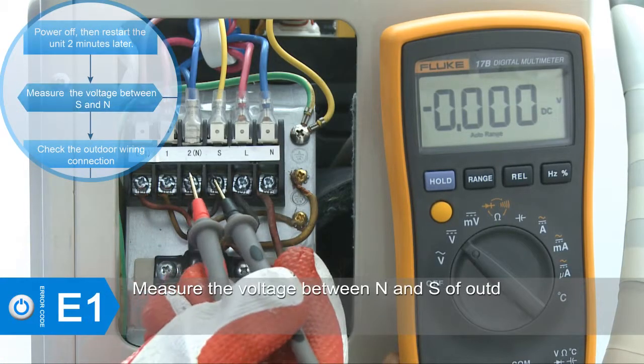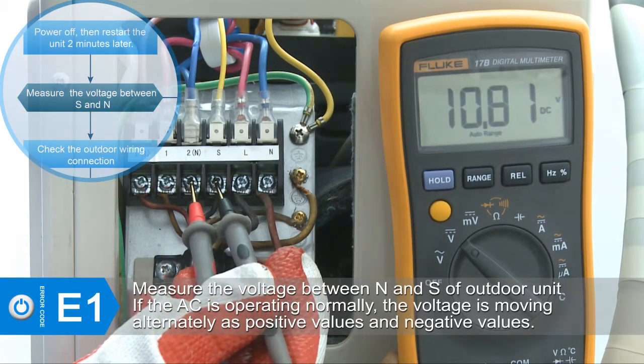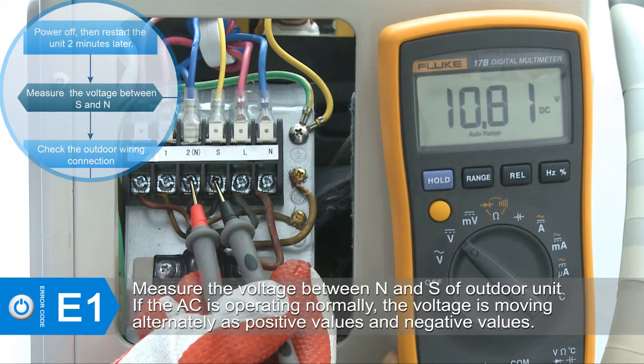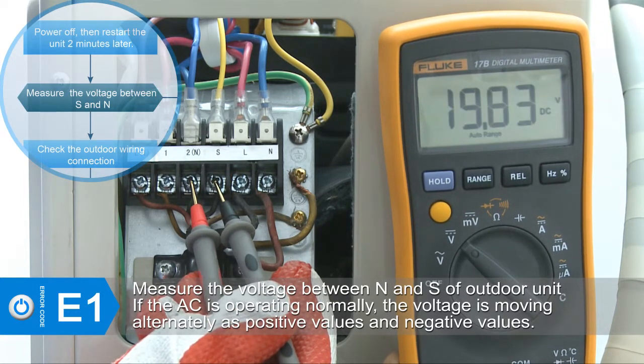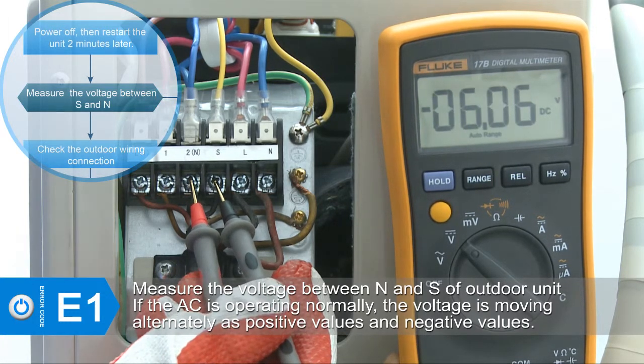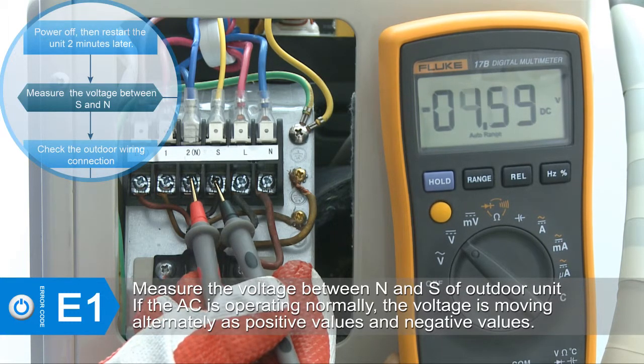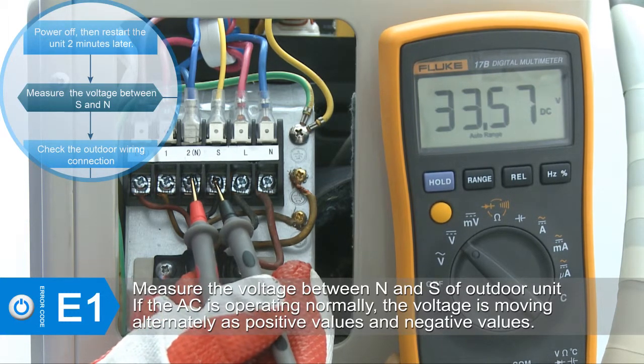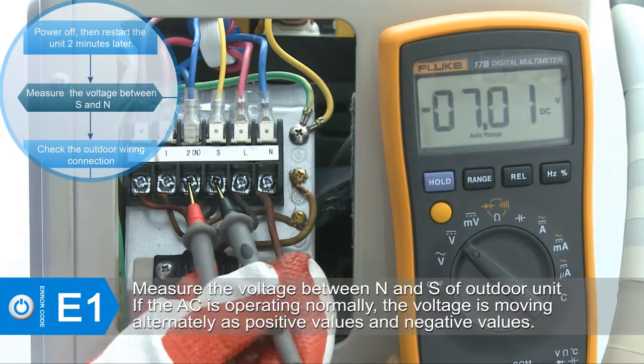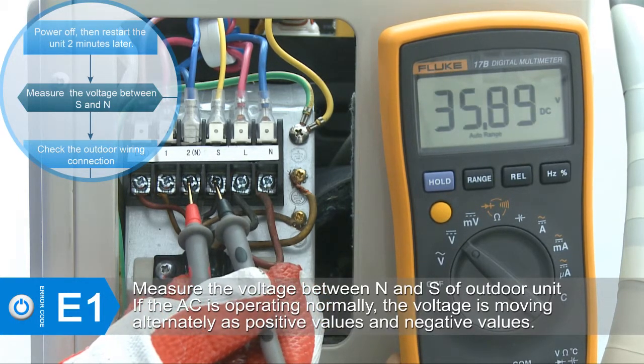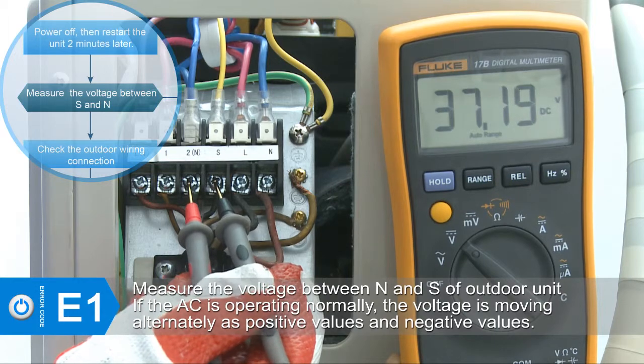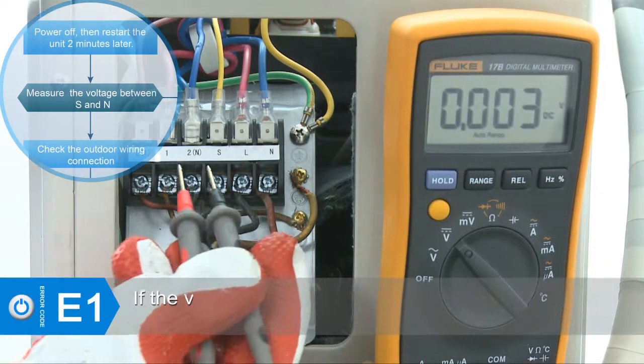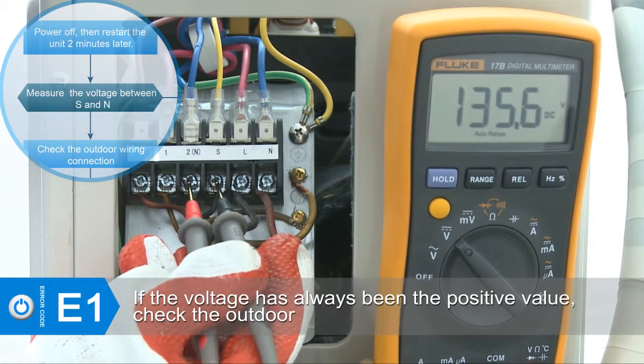Measure the voltage between N and S of the outdoor unit. Select the voltage DC position, then connect the red pin of the multimeter to the N port and the black pin to the S port. If the AC is operating normally, the voltage moves alternately between positive and negative values.